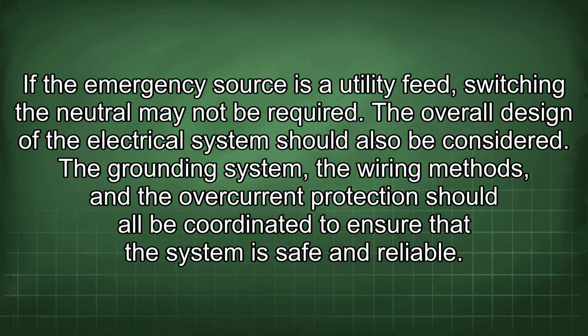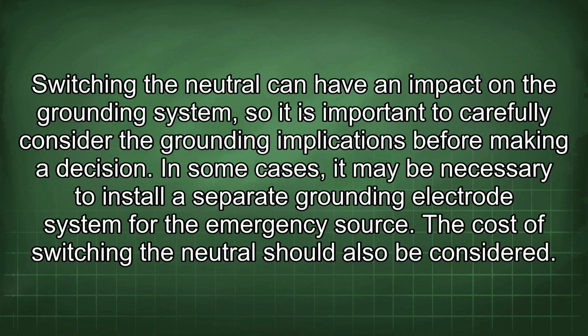The overall design of the electrical system should also be considered. The grounding system, the wiring methods, and the overcurrent protection should all be coordinated to ensure that the system is safe and reliable. Switching the neutral can have an impact on the grounding system, so it is important to carefully consider the grounding implications before making a decision. In some cases, it may be necessary to install a separate grounding electrode system for the emergency source.